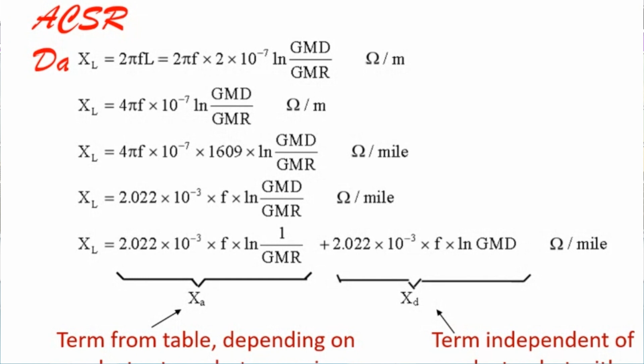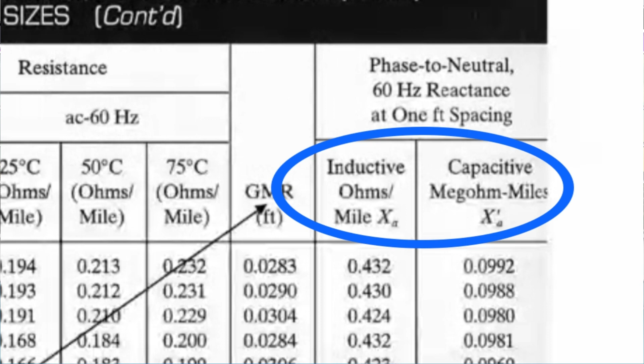With this, all of this is only simple mathematical simplification. They are given here in the data sheet: inductive ohms per mile and capacitive mega ohm mile. This only shows that the inductance has 2 parts - one part dependent on the conductor itself, the other dependent on the distance. They don't care about it. So they give here the inductance and capacitance figures - one dependent on the conductor type, which we'll see now for capacitance, and the other depends on the installation of the transmission line.